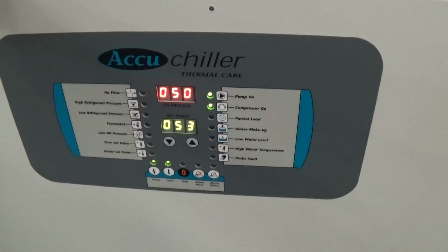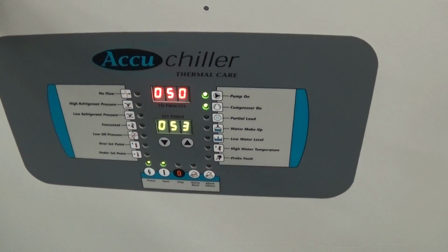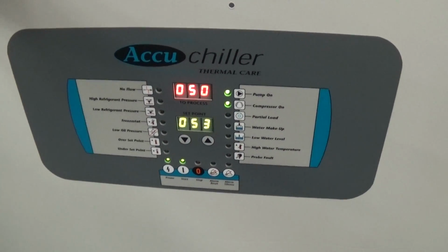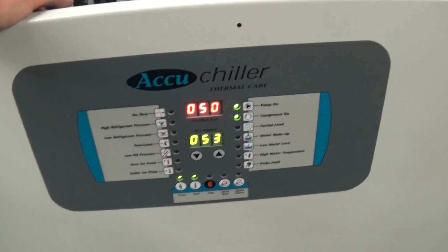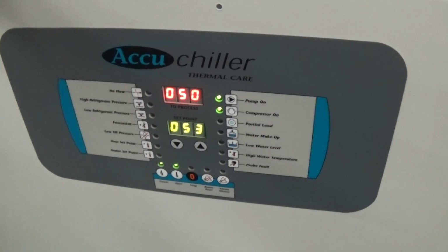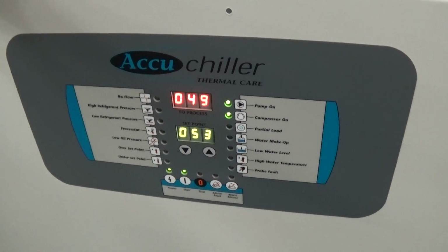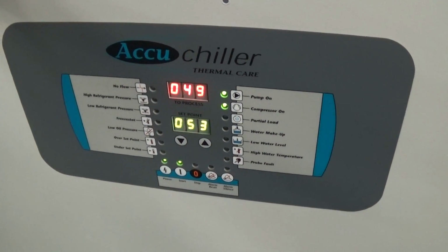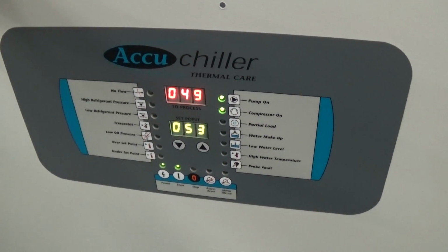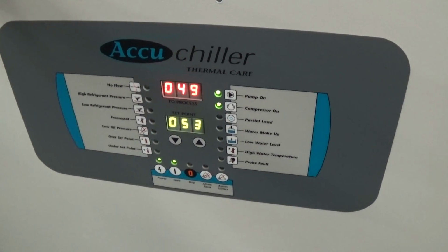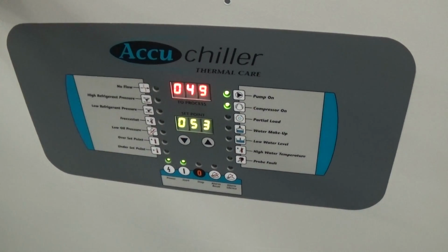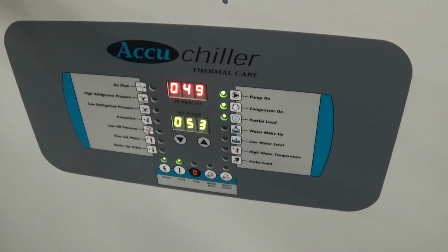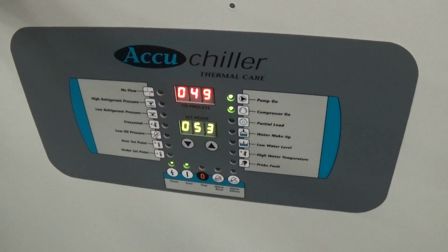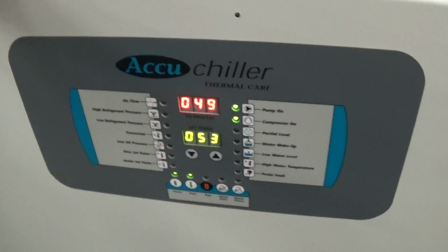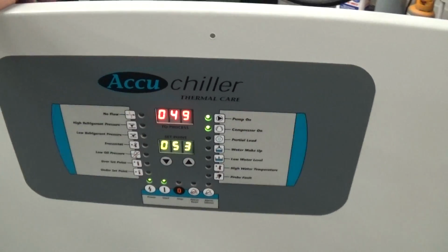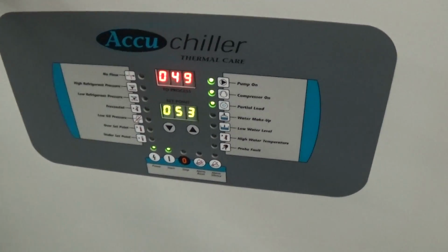not that much. But worth noting, if you're running straight water, I would not run this unit below the 53 degree set point, because at a 53 degree set point, we're still going to get the temperature down to about 48 or so. And what's taking place inside that heat exchanger is more like 30. So if you're running straight water and you've got your fluid temperature at 48, you can start getting into the risk danger range of freezing up the evaporator.